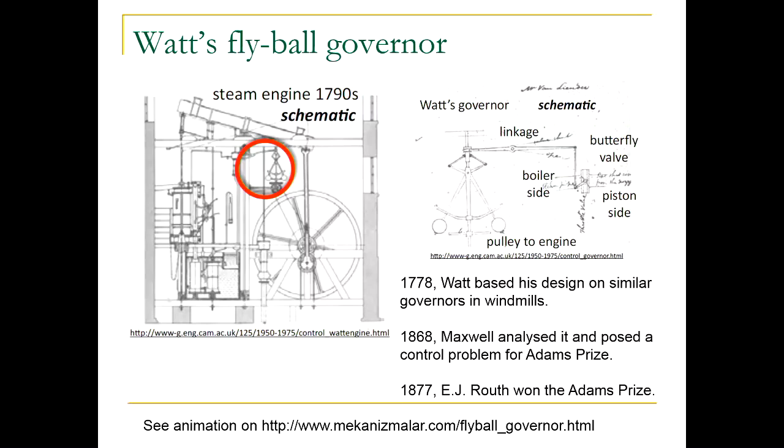But if you connect this movement of these arms to the valve, you can regulate how much you open or close the valve. And if designed properly, and this is crucial, if designed properly, this device could maintain the rotational speed of the shaft constant, or very close to constant, which would basically guarantee quality of the product. Okay?